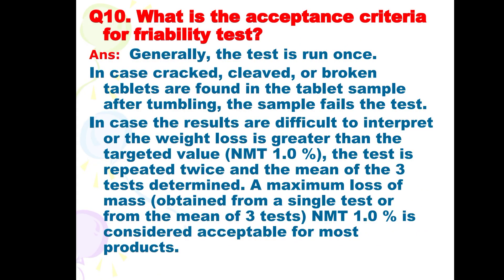Next is: what is the acceptance criteria for the friability test? Generally, the test is run once. In case cracked, chipped, or broken tablets are found in the tablet sample after tumbling, the sample fails the test. In case the results are difficult to interpret or the weight loss is greater than the target value, the test is repeated twice and the mean of the three tests is determined. A maximum loss of mass of not more than 1% is considered acceptable for most products.